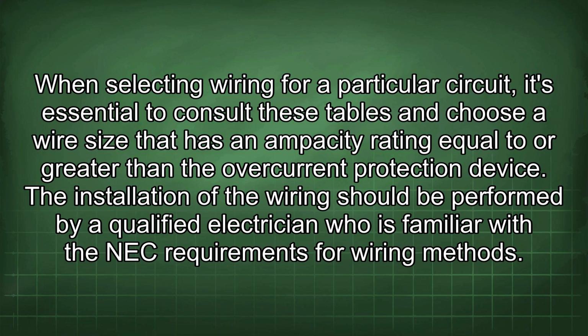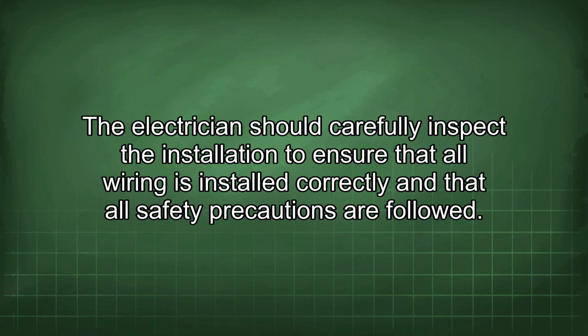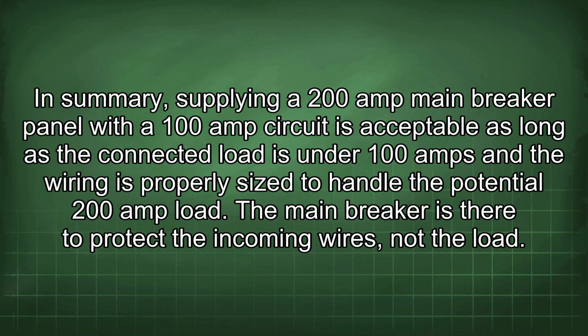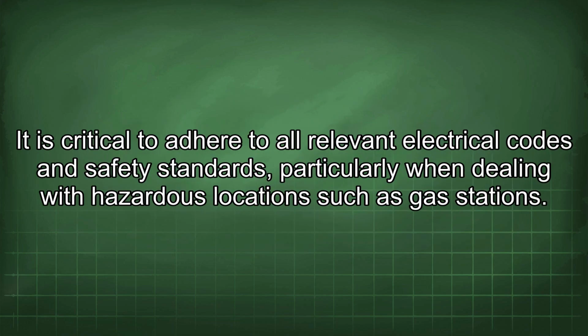The installation of the wiring should be performed by a qualified electrician who is familiar with the NEC requirements for wiring methods. The electrician should carefully inspect the installation to ensure that all wiring is installed correctly and that all safety precautions are followed. In summary, supplying a 200 amp main breaker panel with a 100 amp circuit is acceptable as long as the connected load is under 100 amps and the wiring is properly sized to handle the potential 200 amp load. The main breaker is there to protect the incoming wires, not the load. It is critical to adhere to all relevant electrical codes and safety standards, particularly when dealing with hazardous locations such as gas stations.